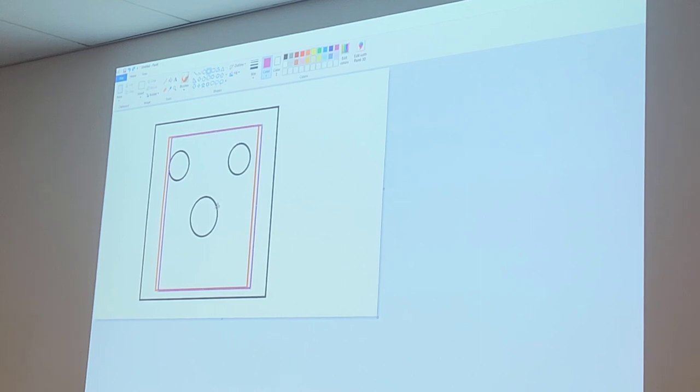On the other hand, we have congruence. Congruence isn't about the center. We could be perfectly centered, but there can still be some differences between the light and the X-ray. And in this case, we are talking about the edges. Right? So, this might be the light, but my X-ray beam might actually be slightly smaller.